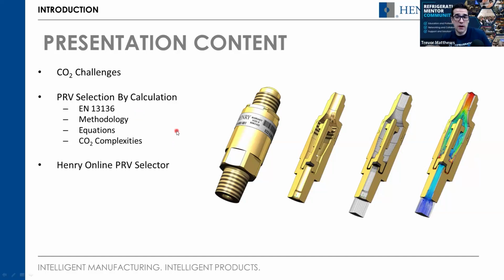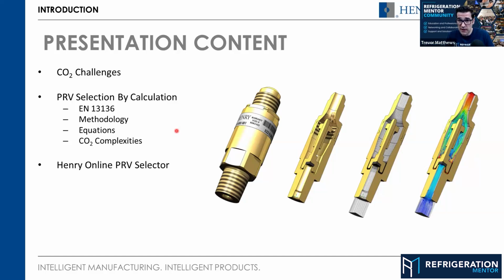And that's a big thing. I want to point that out. Depending on where you're at in the world, there are going to be different codes and regulations. A friend of mine from Copeland sent me a message when I was asking about the pressure relief, and he says per ASME B31.5, the system is to be tested at 1.1 times the design working pressure. But that may be different here in Canada, maybe in the UK or Ireland or Scotland. You could be in Australia, New Zealand, or South Africa. The codes may be different. And then in your province or state, it could be even stricter depending on your local jurisdictions. So this is very, very important.